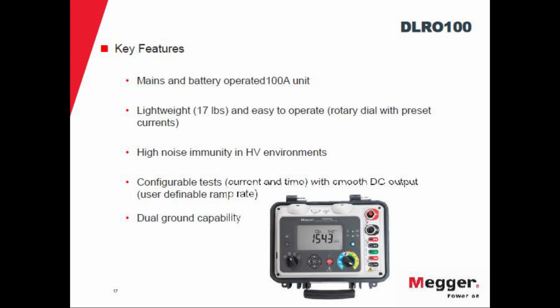Because if you have a higher current than the nominal value, then your resistance will heat up. And if a resistance heats up, the resistance value will change. So you always want to be below the nominal current. Now, why 100 amps? Well, because of these standards for circuit breakers, that's the requirement for those standards.